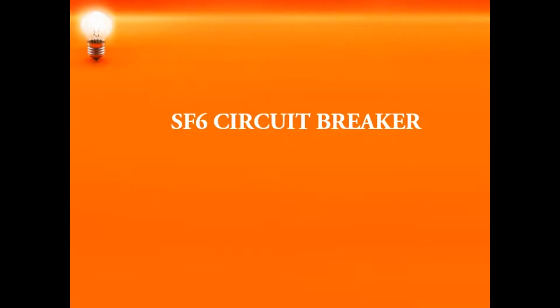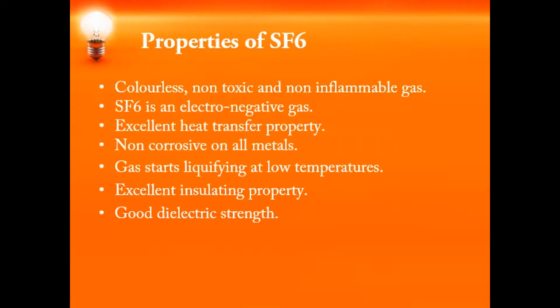Hello everyone, welcome to this session on SF6 circuit breakers. An SF6 circuit breaker is one in which the arc quenching medium is SF6. SF6 is sulfur hexafluoride. It is used as an arc quenching medium because it is non-toxic, non-inflammable, and has a very good dielectric strength and excellent arc quenching property.